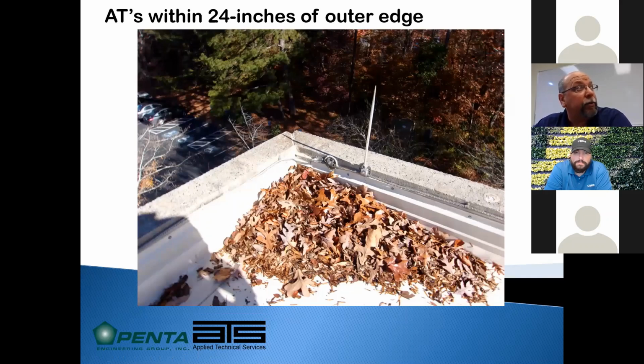And as I mentioned, air terminals need to be within 24 inches of an outer edge. In this instance, the original air terminal was within 24 inches. It got broken, and the replacement contractor installed one that was more than 24 inches. So when we did our evaluation, we noted that, and we had to basically remove both of these and install one within 24 inches. And if you remember from one of the earlier photos, several of those photos were where lightning has struck the corners of the building.